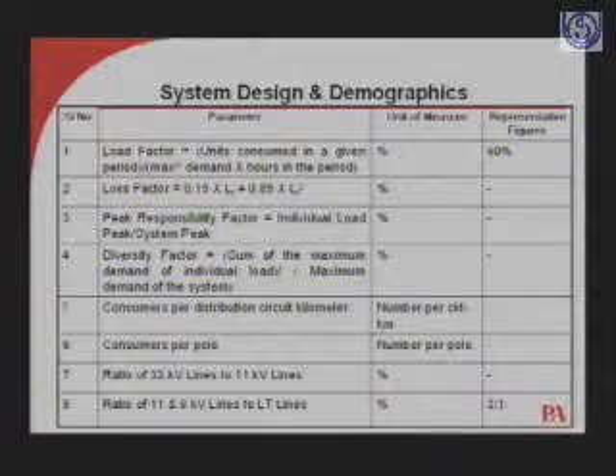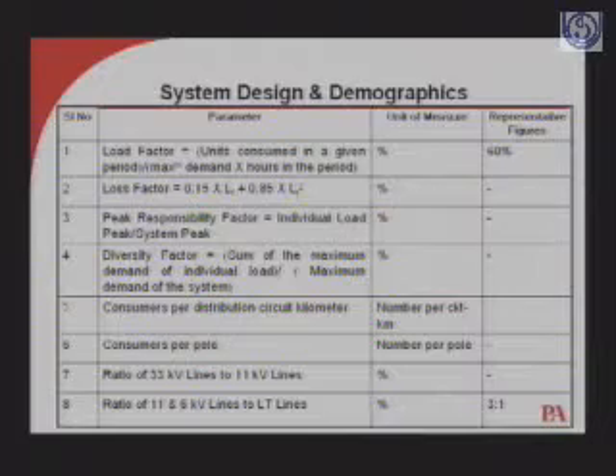Similarly, peak responsibility factor. You see, there can be many individual loads in a circuit, but while doing system planning, you have to think that these loads cannot be summated to get the maximum demand, because therefore we have the diversity factor. At the same point of time, these loads will contribute to a certain extent in the system peak. So that contribution is articulated through the peak responsibility factor.